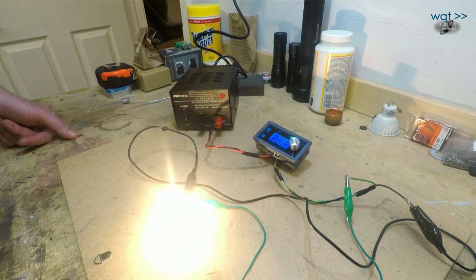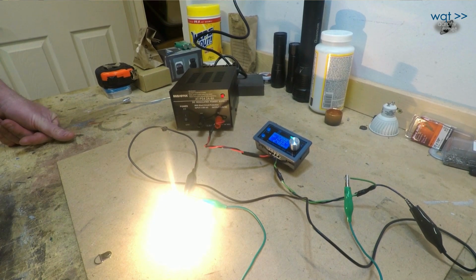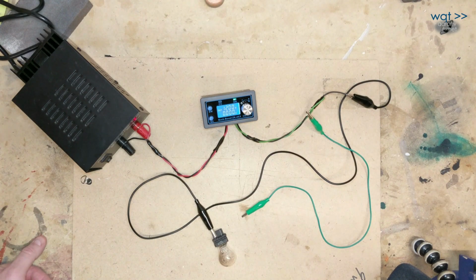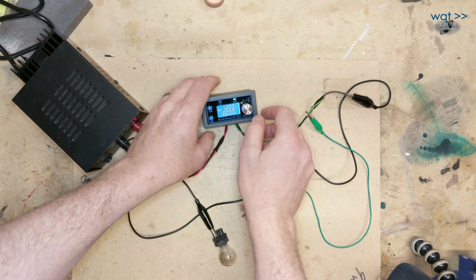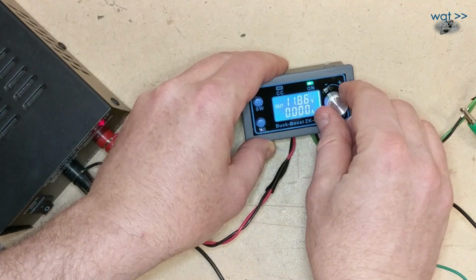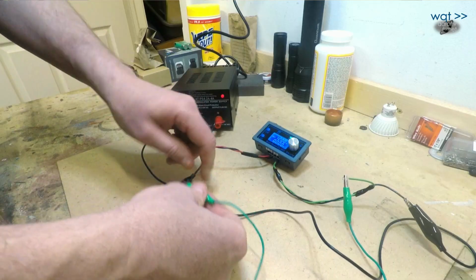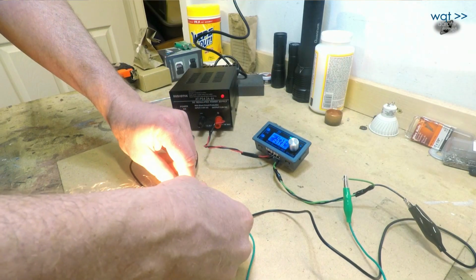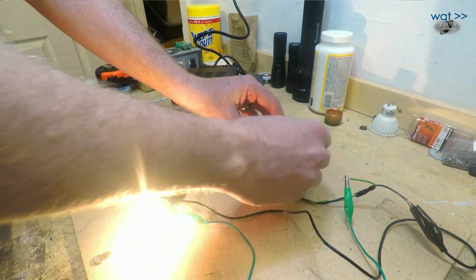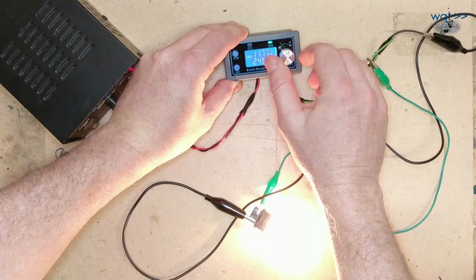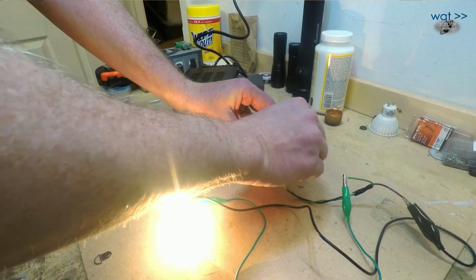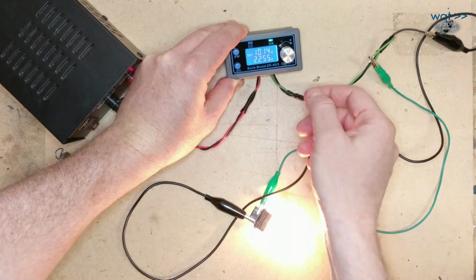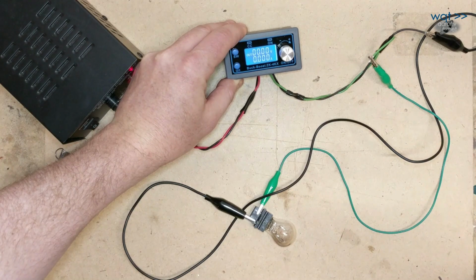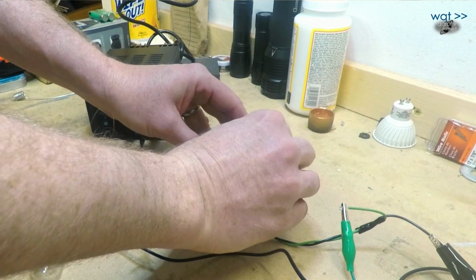So it cycles pretty gracefully, doesn't seem to have any issues supporting the load. This same knob, if you just want to do some fine adjustments without going into the settings, you can start turning it and the output voltage starts changing. So once again, let's connect this, get our 2.5 amps going. As I turn the voltage down, I should also see the current drop, and the bulb will gradually get dimmer. That seems to be happening, and it's very graceful. It is correctly slewing the voltage down into the load. No issues. I can also turn it off. Done. So that's the basic operation right there.